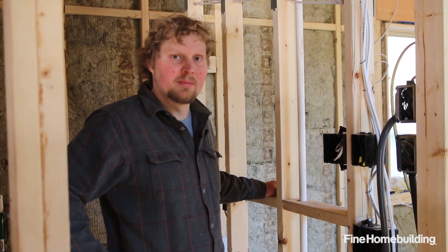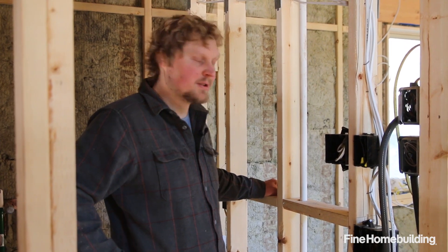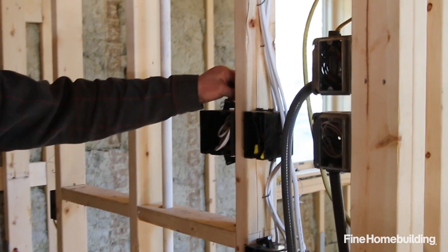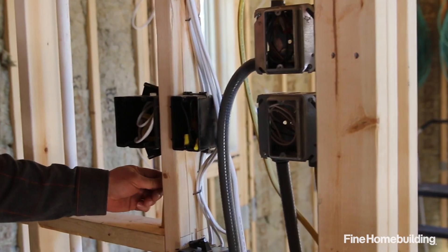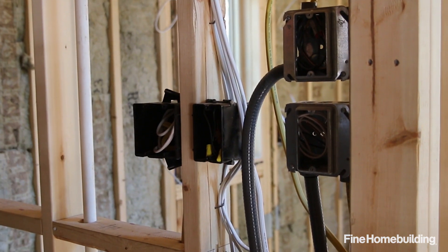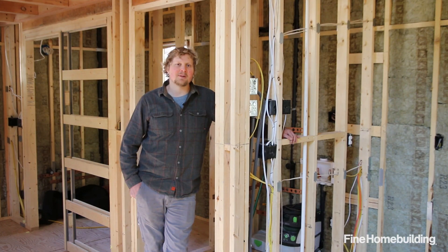We're here in the mechanical laundry room for the last piece of the HRV installation — the control box. We have two low voltage lines running from each unit and a dedicated circuit. We'll put the switch in here with the computer module and that will control the units. I've got the mechanical systems rough-in complete and I'm feeling really good about the two systems working together. The mini-split will provide a constant stream of warm and cool air, and the HRV will provide fresh air and balance moisture between outside and inside.